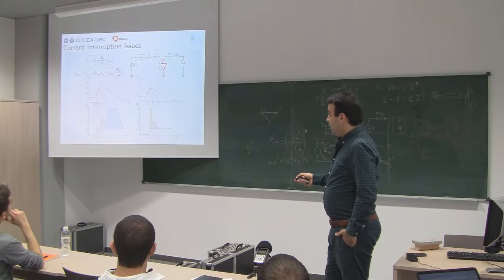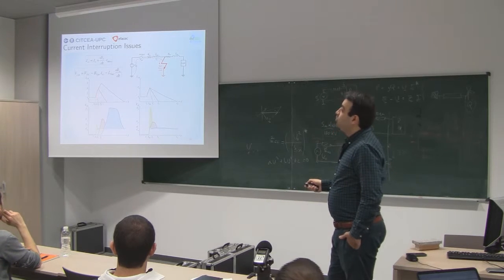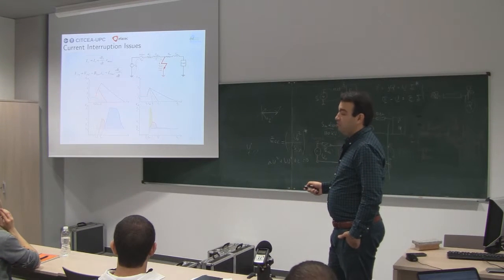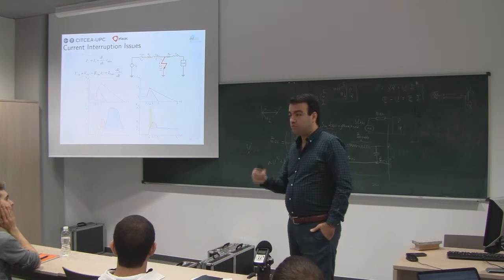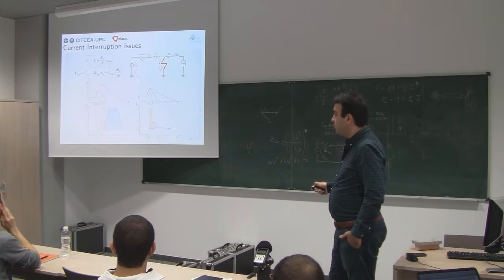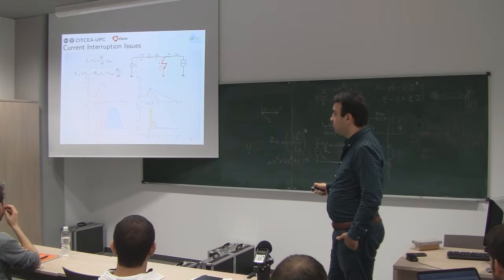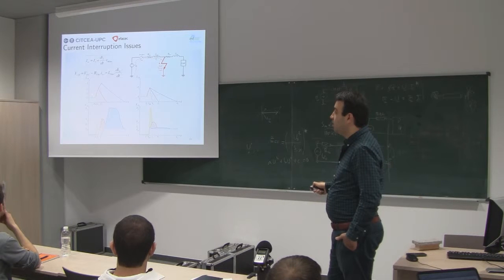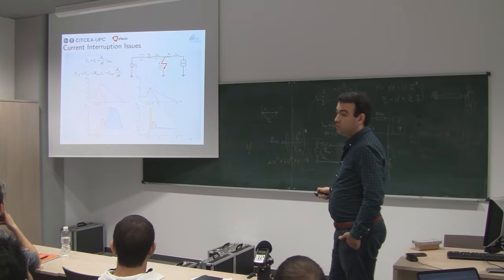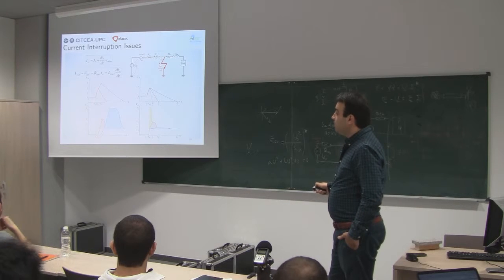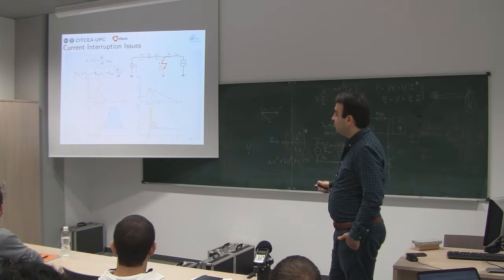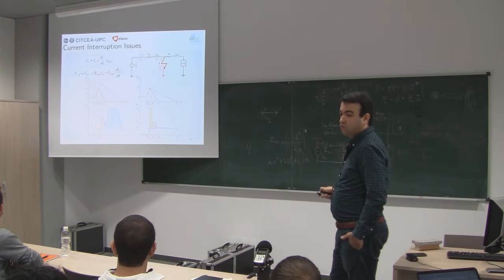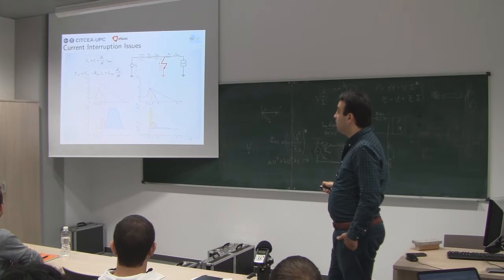this current. And if you try to identify, to start the fault interruption process faster, like this yellow curve, this is the fault current, it is going up, and we start the interruption here, so we will have less transient voltage. But if we have a delay in starting the interruption process and interrupt like this, we will have larger transient overvoltage.